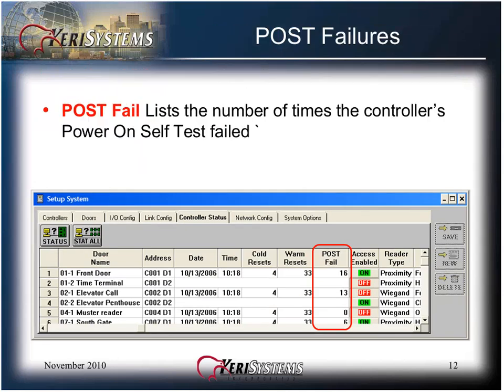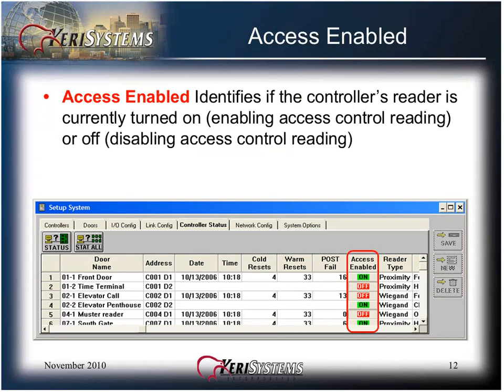A POST fail lists the number of times the controller's power-on self-test failed. This is indicative of a RAM or controller power issue. One is okay; more than one needs to be investigated. The access enabled column identifies if the controller's reader is currently turned on, enabling access control, or off, disabling access control reading.